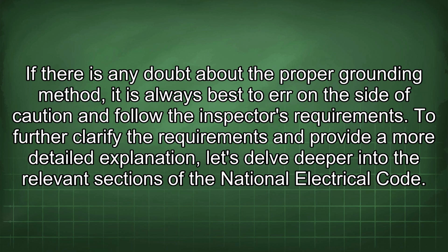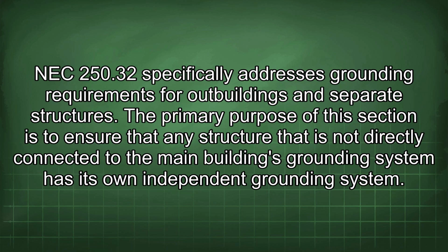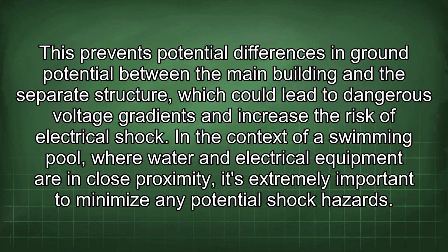To further clarify the requirements and provide a more detailed explanation, let's delve deeper into the relevant sections of the National Electrical Code. NEC 250.32 specifically addresses grounding requirements for outbuildings and separate structures. The primary purpose of this section is to ensure that any structure that is not directly connected to the main building's grounding system has its own independent grounding system. This prevents potential differences in ground potential between the main building and the separate structure, which could lead to dangerous voltage gradients and increase the risk of electrical shock.